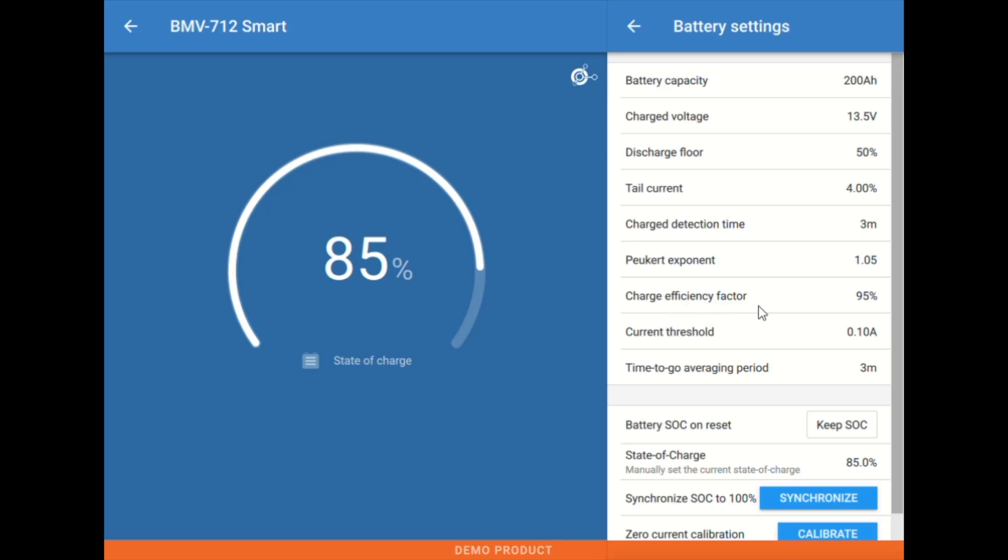Next up here we have a charge efficiency factor. 95% is typically what we're going to use for lead chemistries, maybe 96, again for a higher efficiency lead or a small bank. And then we would be putting this 98, 99% for most lithium applications.